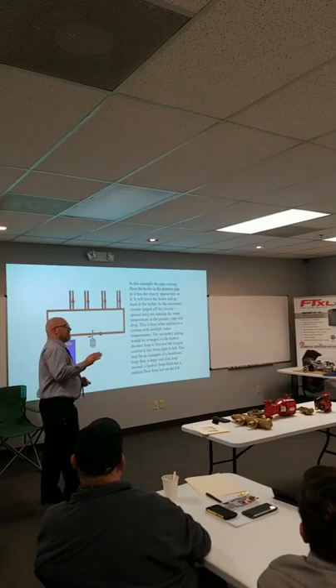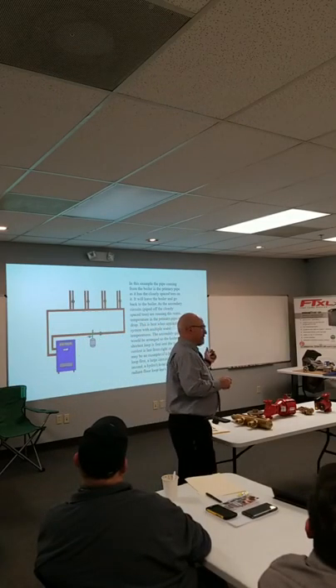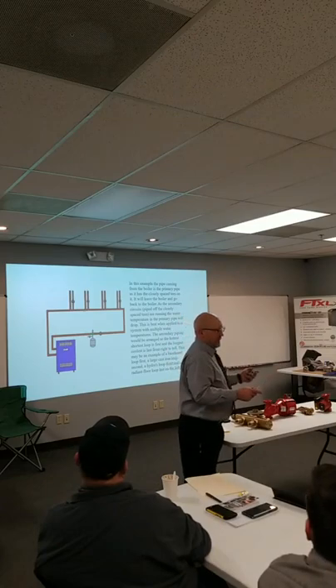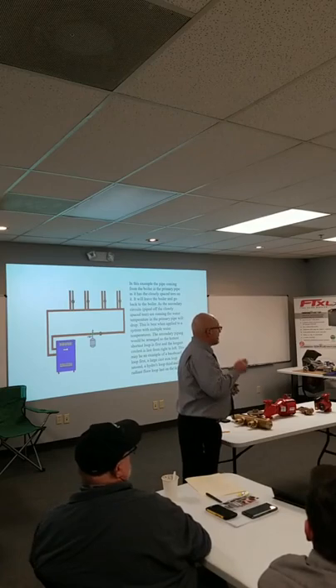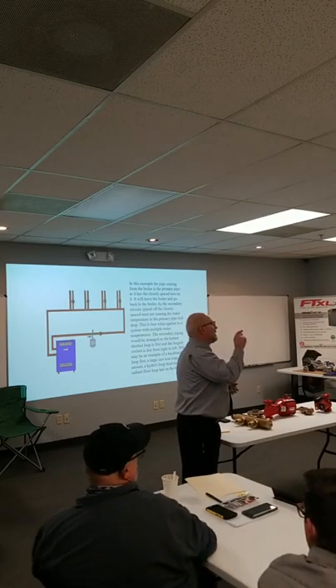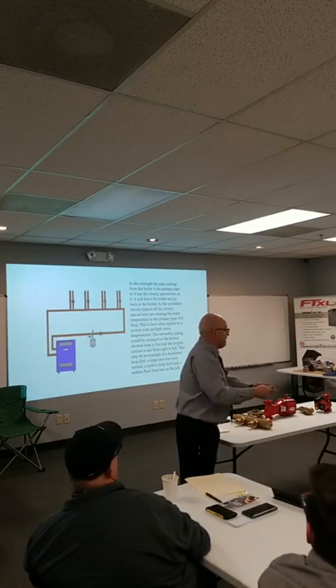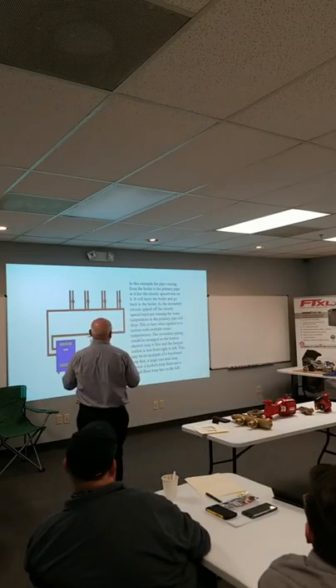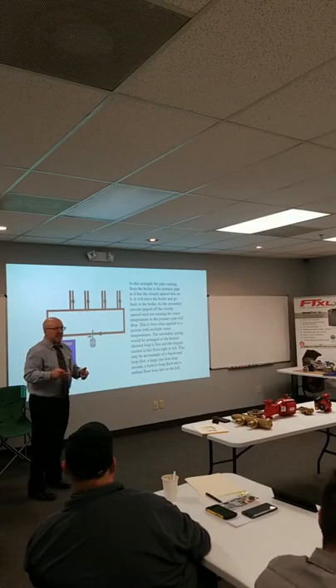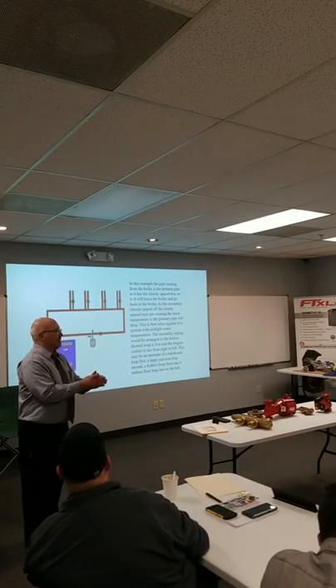You know what I hate though? I hate when I tell somebody to pipe it with closely spaced tees and I go out and it's 12 inches, because that's what the book said. And I hear that a lot. Well, that's easy to tell the helper, 12 inches. But it's awfully nice to know that somebody actually opened the book, right. Which is good. So they saw something, but they saw the wrong thing. But it's four pipe diameters, and I don't care if it's primary or secondary, closely spaced tees, if you're using primary, secondary, they have to be four pipe diameters max. Okay?